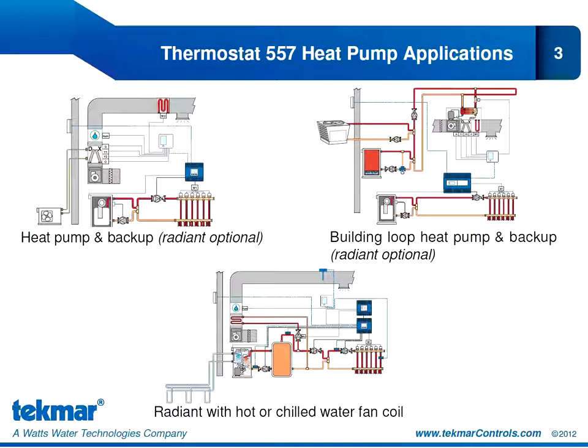Now, the 557 was designed for these heat pump applications, but I do want to emphasize that it is not limited to being just a heat pump thermostat. It is also perfectly suited for 2-stage heat, 2-stage cool applications with traditional heating and cooling equipment instead of heat pumps. And we'll look at those applications first over the next 2 slides.